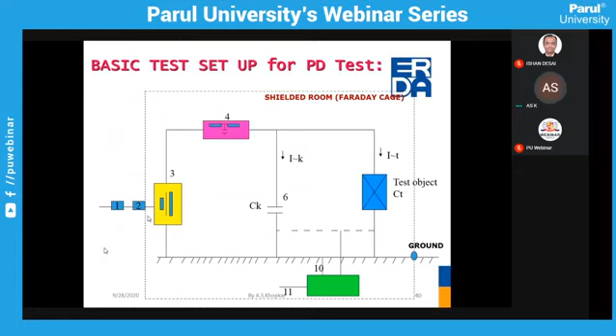Number 10 and number 11 are the PD meter, on which we measure the partial discharges, and this is the test object, a CT. Everything is on a common ground. This line shown is the common ground of the high voltage transformer, coupling capacitor, partial discharge meter and test object. Everything is kept inside the shielding room except the filters and isolation transformer. This is a typical photograph of ERDA, inside the partial discharge room.